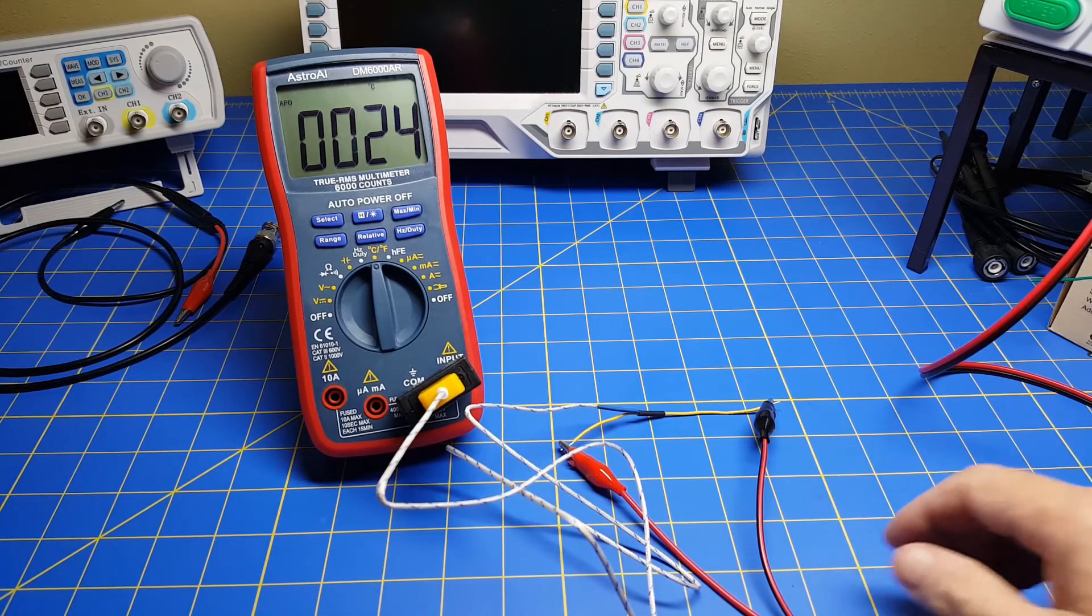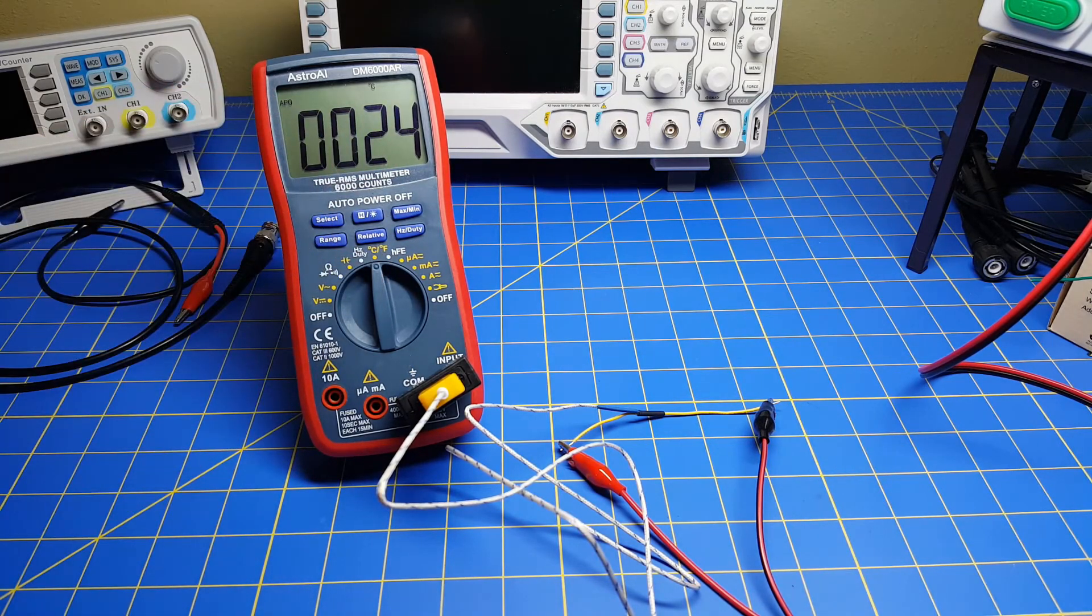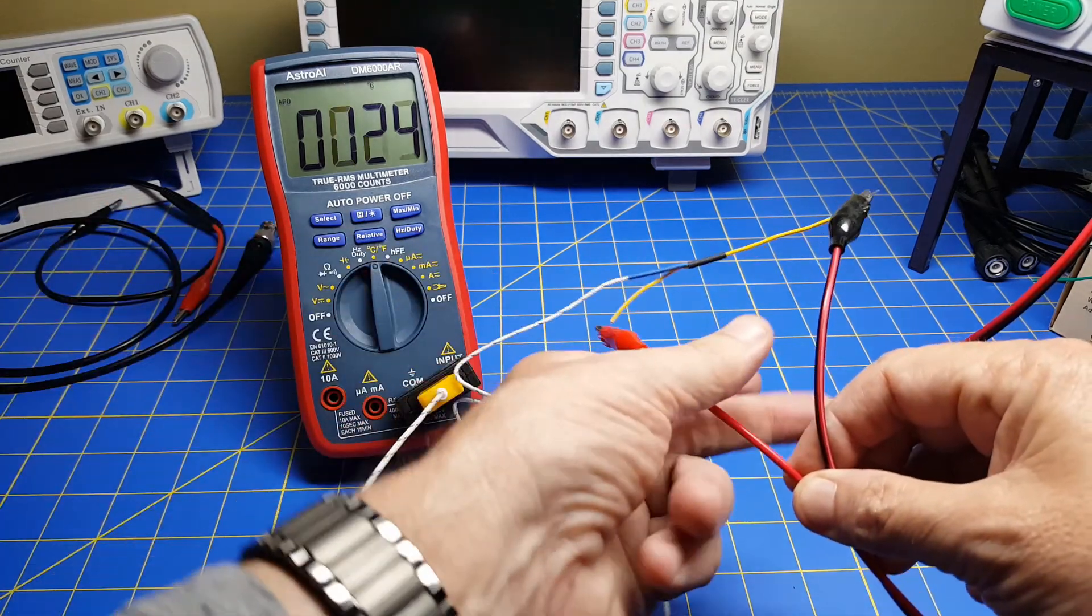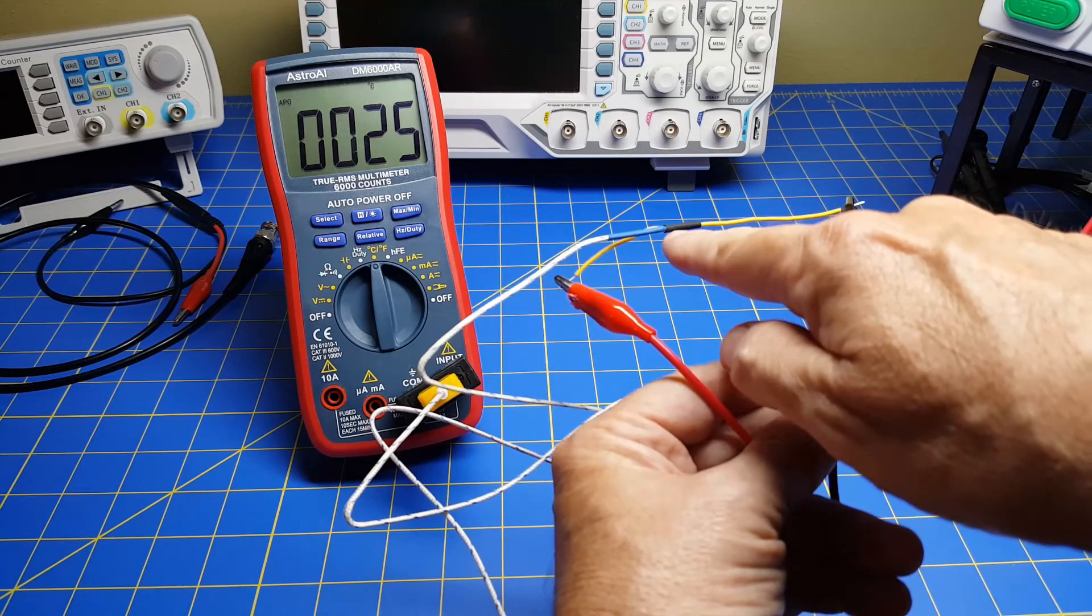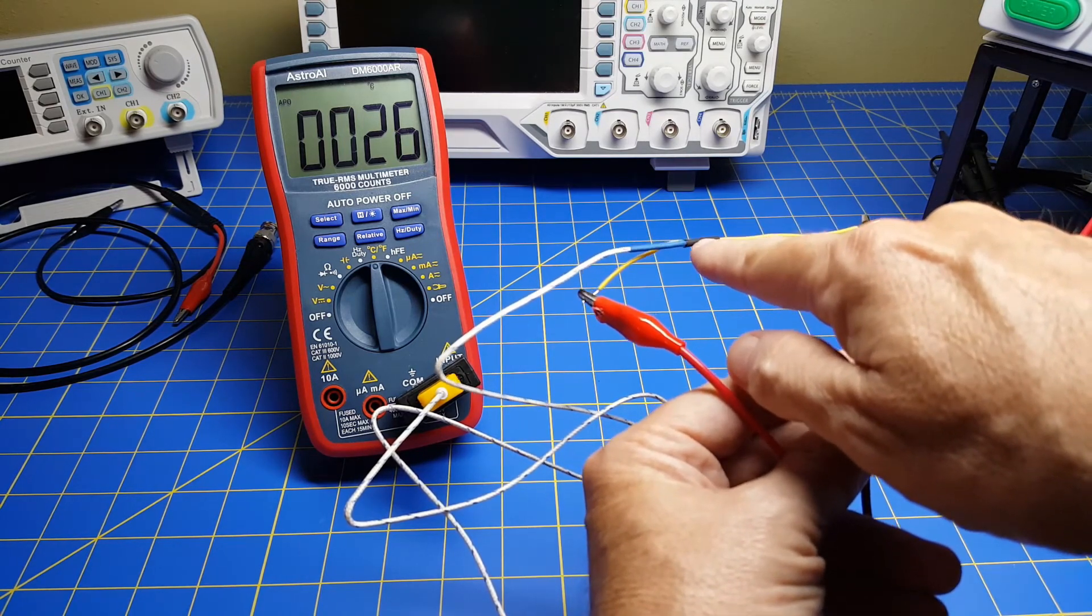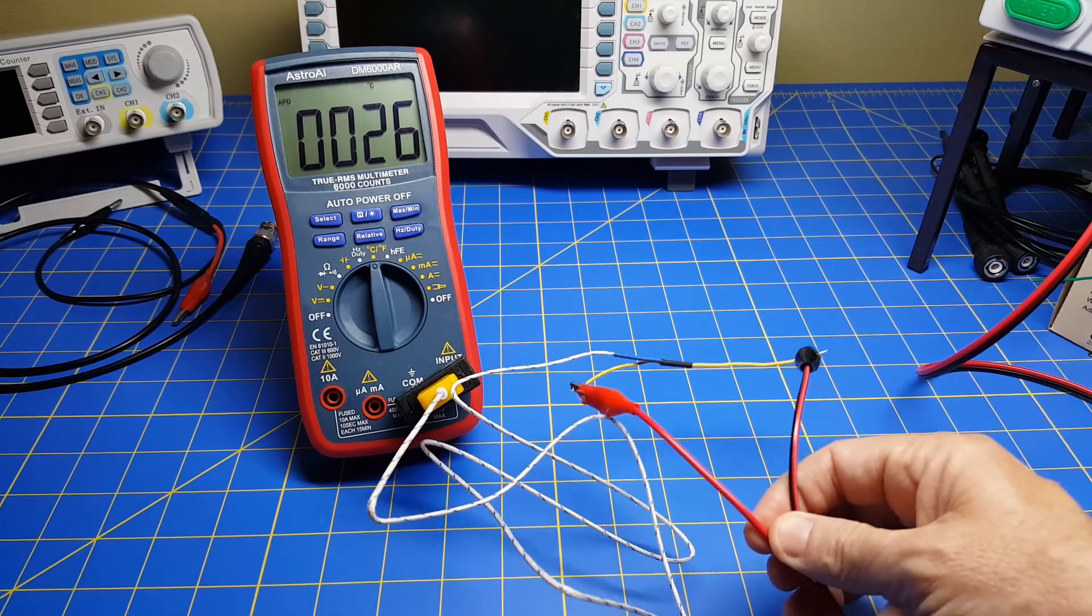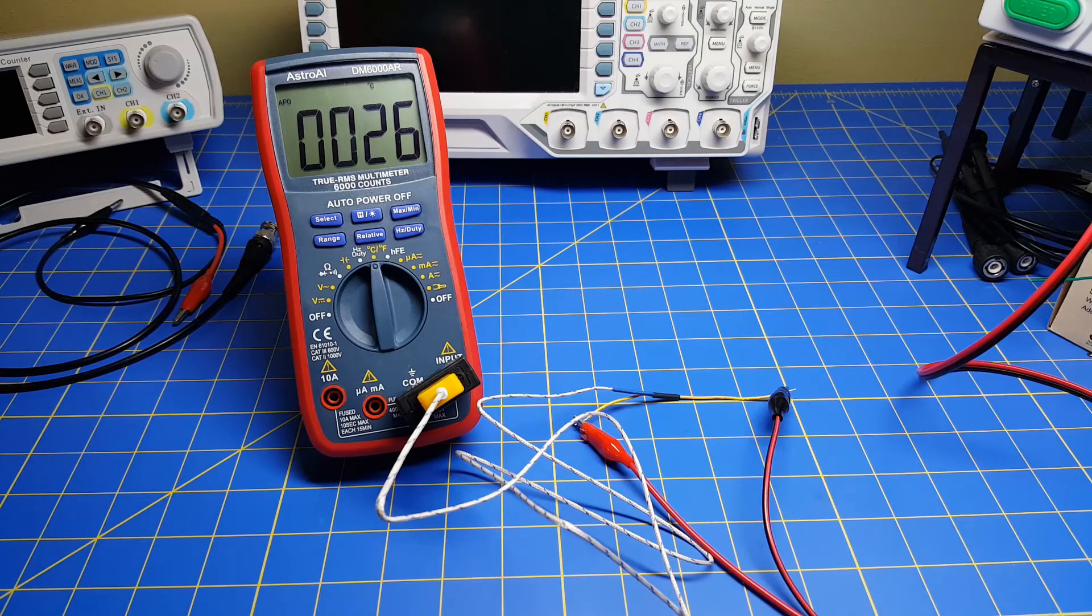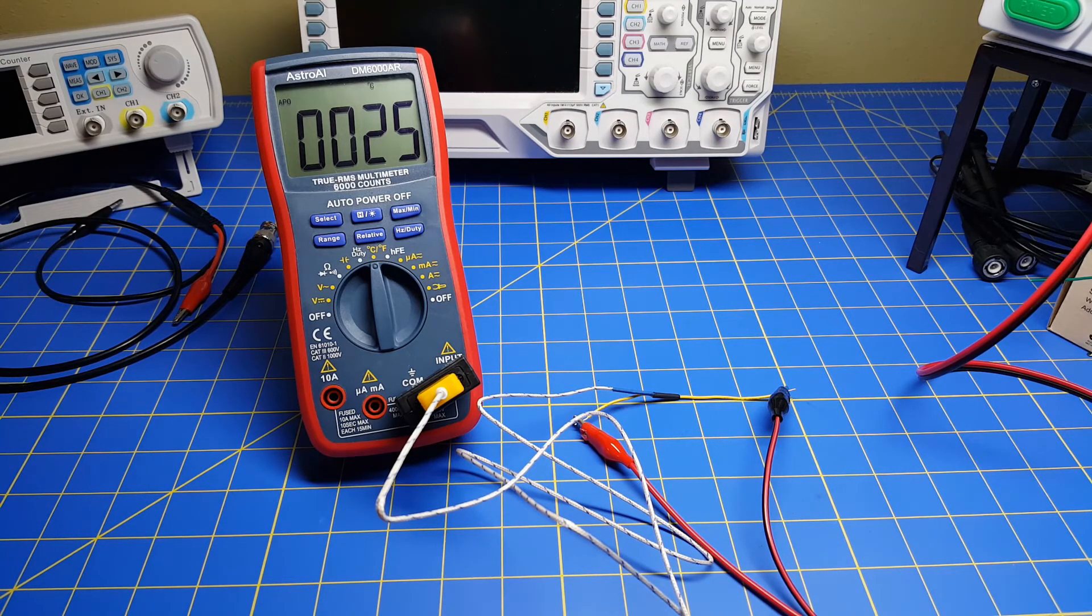Okay, so what I've got here is I've got my multimeter and I've got a thermocouple. And it's set on degrees centigrade. It's measuring normal room temperature. And I have connected that thermocouple to a piece of number 22 wire. And I've taken off some of the insulation and used some Kapton tape, which is thermal tape, to connect the thermocouple to touch the wire. And I also put some heat shrink over it to kind of simulate an insulation, to kind of double for this PVC insulation that I took off. So what I'm going to do is I'm going to actually apply 8 amps to this. And you saw in the table, it says number 22 AWG is rated for 8 amps. So I'm going to push 8 amps and we're going to see what the temperature does over a few minutes time.